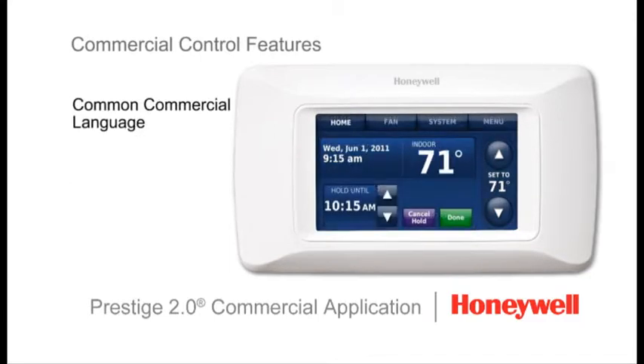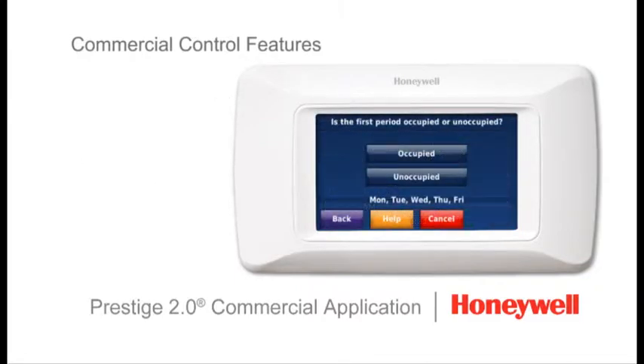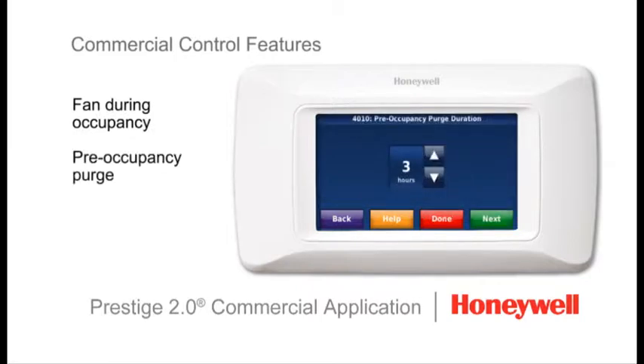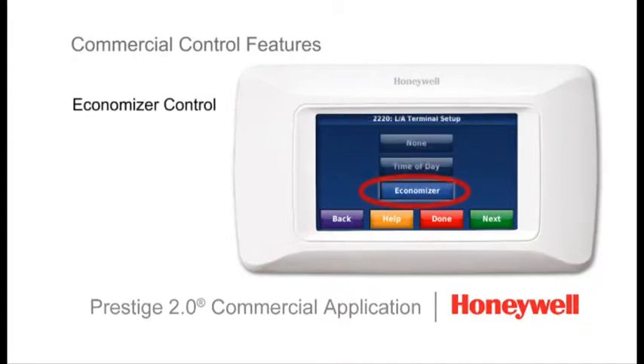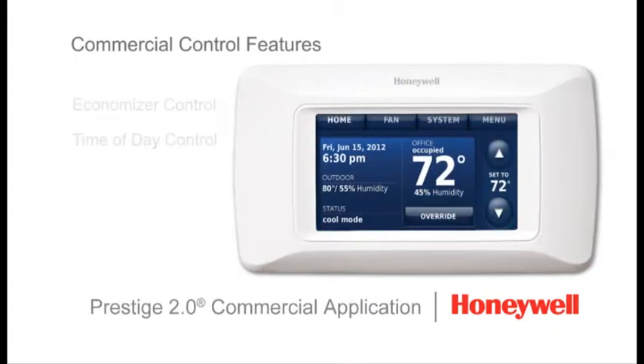Using common commercial building language, such as occupied, unoccupied, and holiday. Defaulting the fan to run during the occupied times. Purging the conditioned space prior to occupancy through the pre-occupancy purge settings, enabling an economizer for ventilation and free cooling, and so much more.